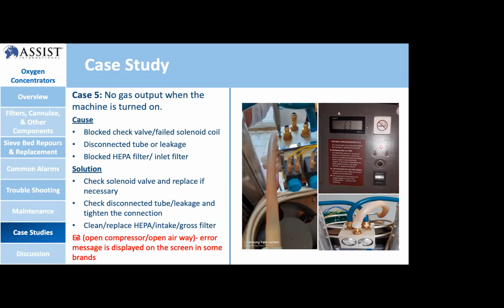And we clean and replace the HEPA filter, intake or gross filter. We did all this. We cleaned the HEPA as well as the intake and the gross filter, and we dry them, then we replace them, so that the machine is properly working, that means it gives normal oxygen concentration at the output.